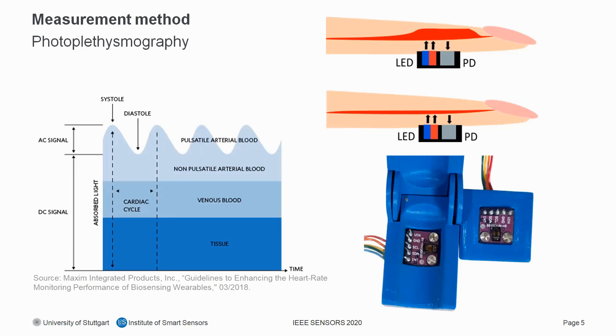What is photoplethysmography? It is an optical volumetric measurement of an organ. A light-emitting diode illuminates the skin and a photodiode detects changes in light absorption — when a pulse wave arrives there is more absorption, and when there is no pulse wave there is less absorption. A PPG signal contains a DC and an AC component. The DC component contains information about non-pulsatile tissue and average blood volume, while the AC component changes synchronously with each heartbeat due to changes in blood volume. For heart rate, blood pressure, and oxygen saturation measurement, only the AC component is needed.